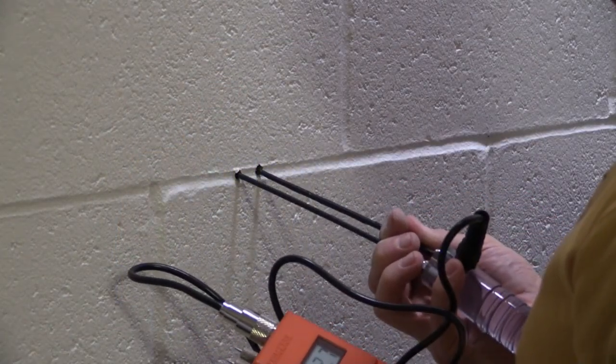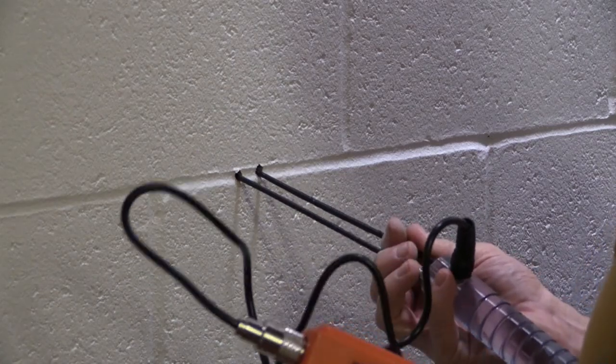Another alternative is to drill holes through the shell of CMU, for example, and insert the probes into the holes. A relative scale is used to determine moisture content. That is, specific moisture percentages are not provided.